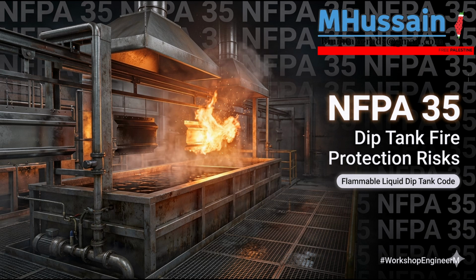Correct. And the placement of that makeup air is just as vital as the exhaust. If the fresh air supply vent is located too close to the floor exhaust vent, the air will short circuit. What does that mean, short circuit? The fresh air comes in and gets instantly sucked right back out, leaving the rest of the vast factory floor completely stagnant.